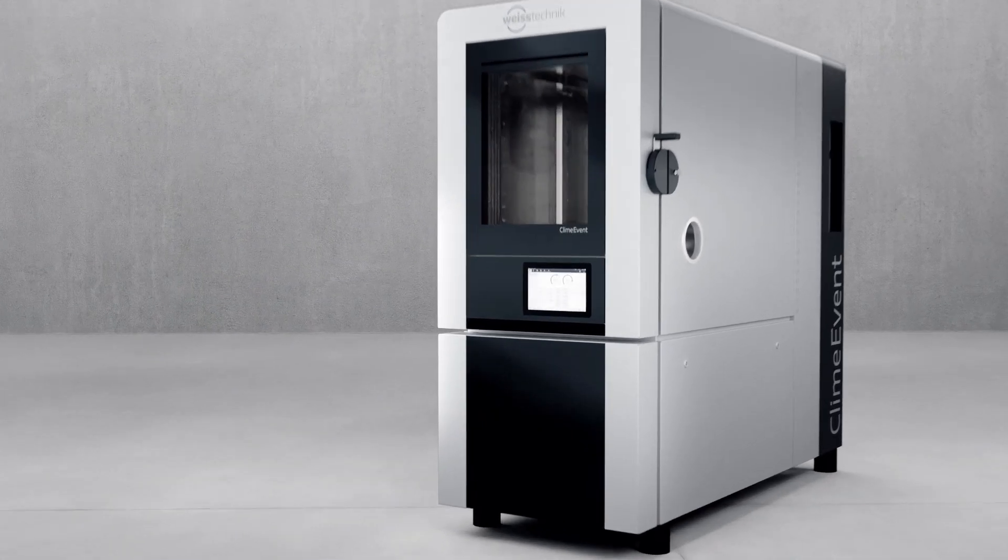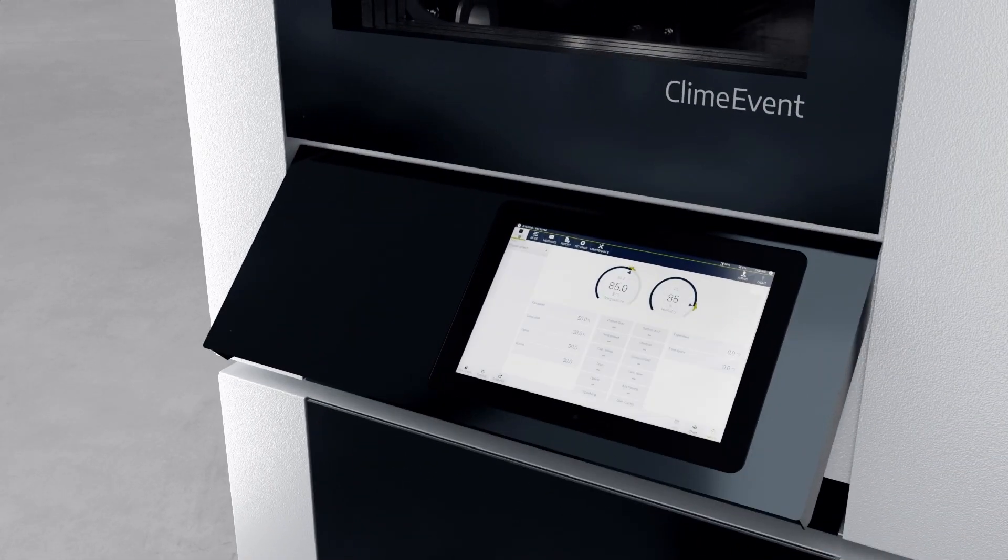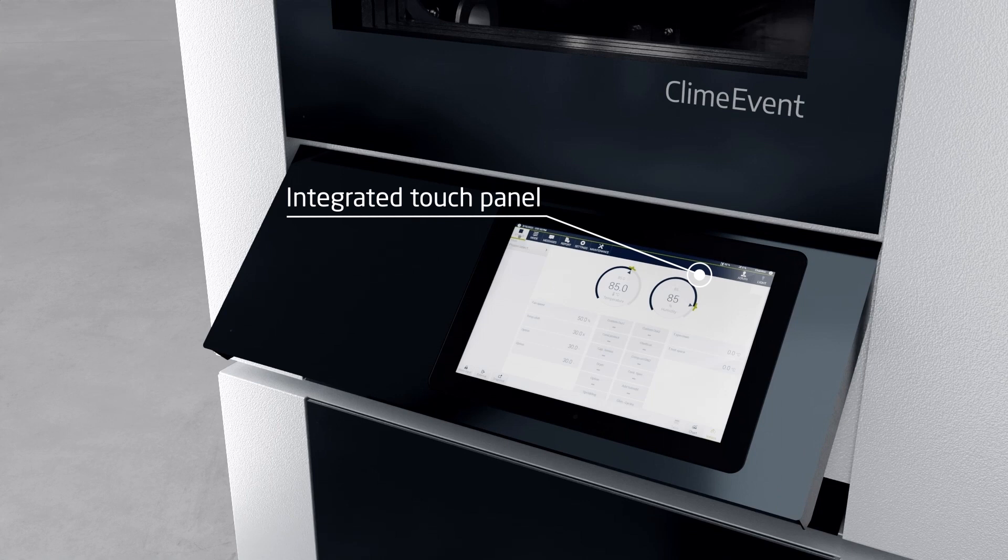The 10-inch touch panel integrated into the front of the device can be folded out up to 60 degrees. With the WebSeason remote control software, you can program, control, and monitor the unit anytime and anywhere conveniently via tablet or smartphone. Data from multiple sensors can be recorded and displayed. The multi-user concept allows simultaneous access by several users and user-specific saving of settings such as language and units.